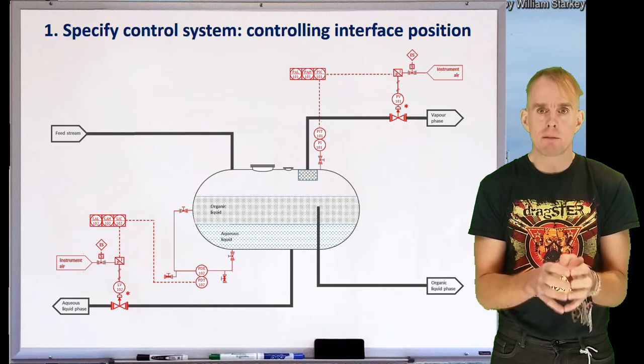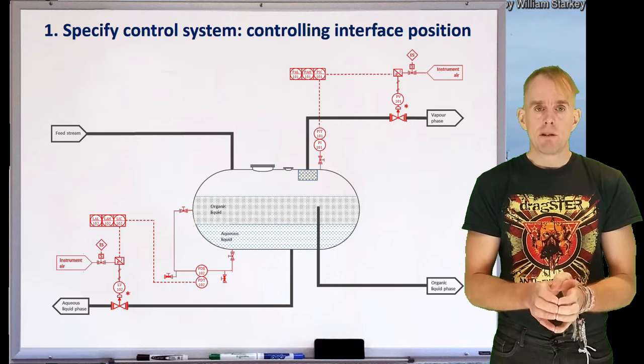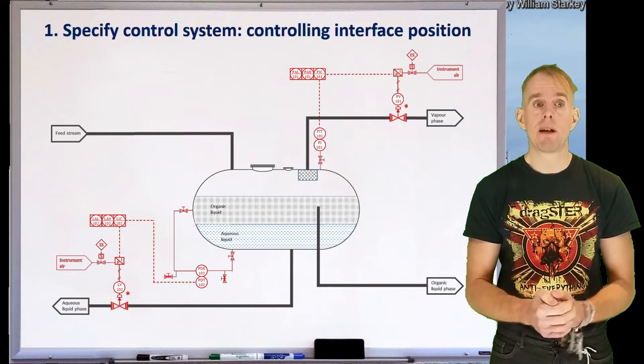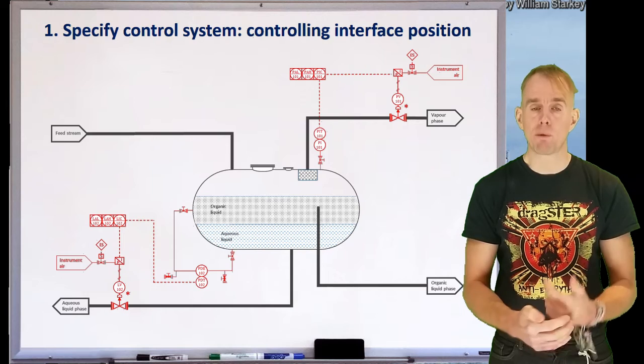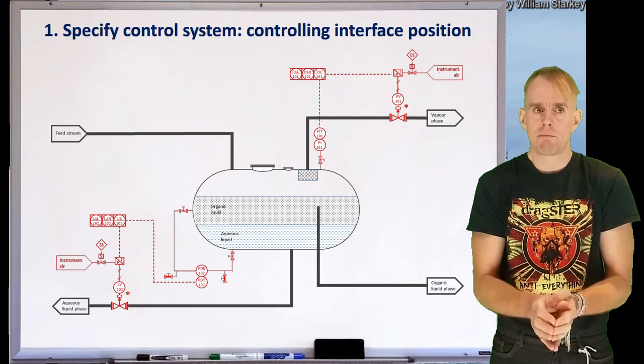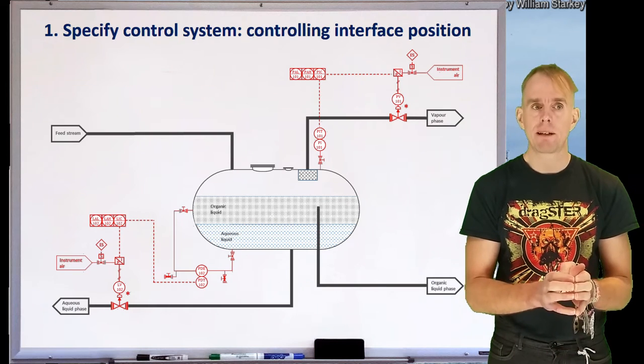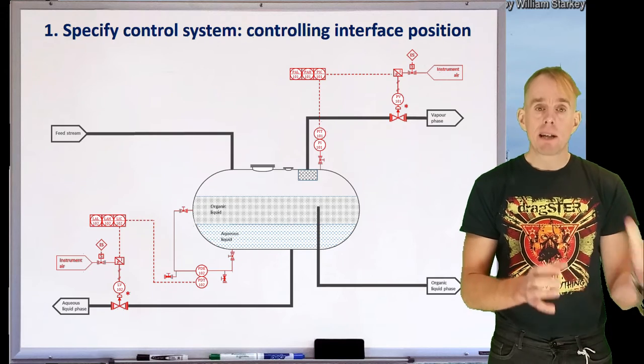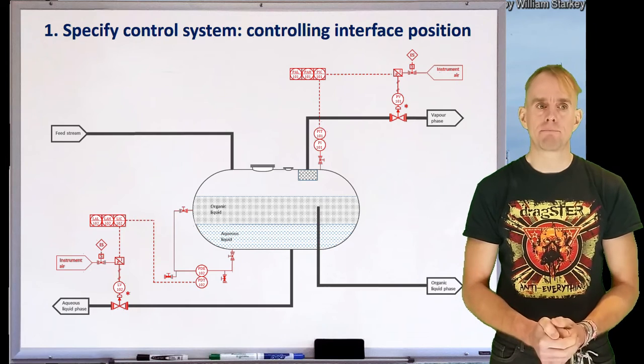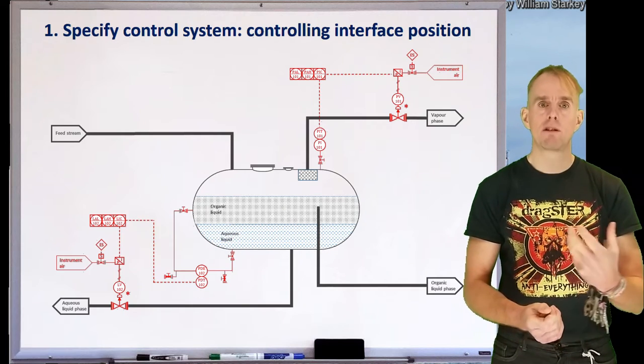The two small-bore pipelines also have drains associated with them — those two normally closed valves. Taking the differential pressure measurement from the static head in the left-hand and right-hand tubes, we convert it into an electrical signal — 4 to 20 milliamps — and take that forward to a level controller. So we take pressure information and infer level information from it. That is the job of the level indicator controller, the LIC. We also have two alarms: a high-level alarm and a low-level alarm, which are informational and will alert the operator.